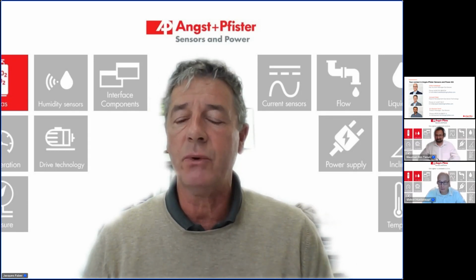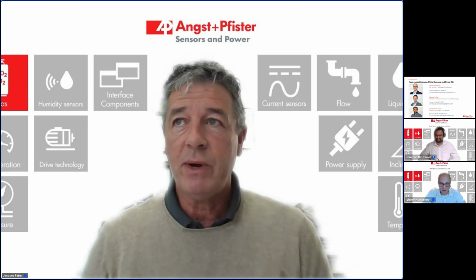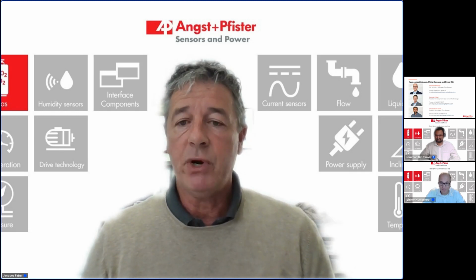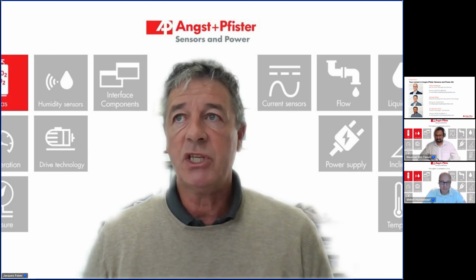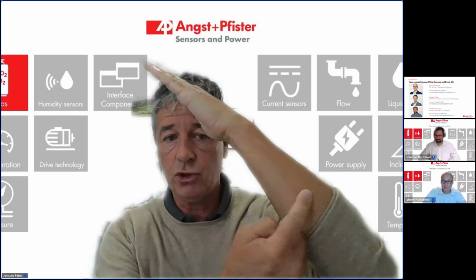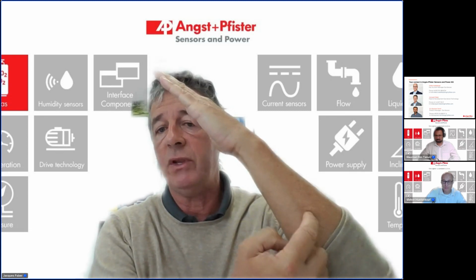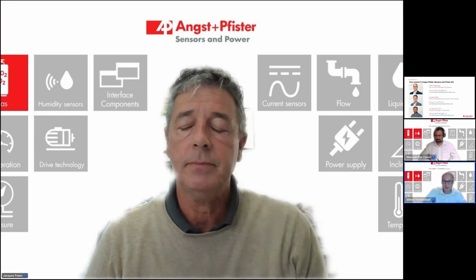Okay. I see one question that I would like to quickly answer, because it is asked very often. Do you need a 2-point calibration or only 1 point? That's a very important one. At the beginning, you need a 2-point calibration, but afterwards, if you have a stable condition, then it's also possible to do only 1 point. Meaning just a zero point, because the inclination is given by the 2-point calibration. Afterwards, if the inclination is right and you are in a steady environment, you can just do the zero point and you will have good results. But sometimes it makes sense to do the 2-point calibration.